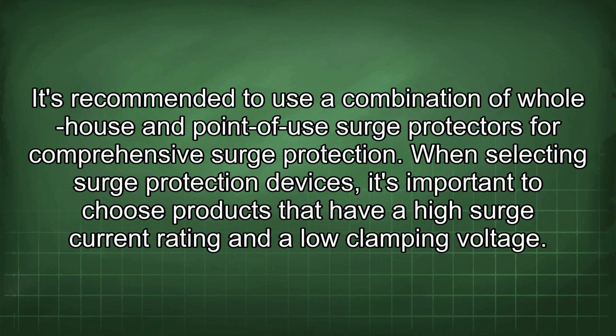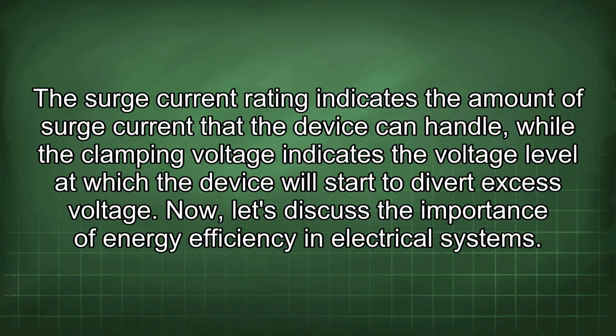When selecting surge protection devices, it's important to choose products that have a high surge current rating and a low clamping voltage. The surge current rating indicates the amount of surge current that the device can handle, while the clamping voltage indicates the voltage level at which the device will start to divert excess voltage.